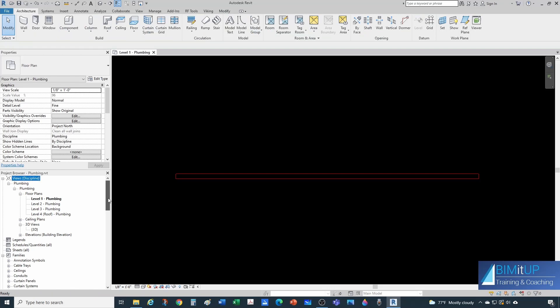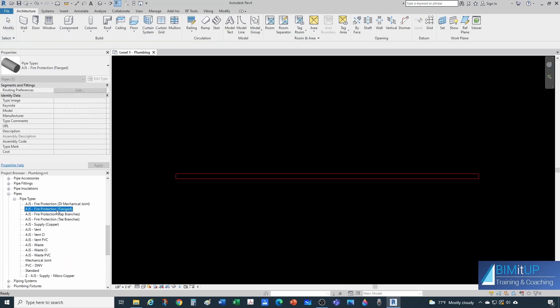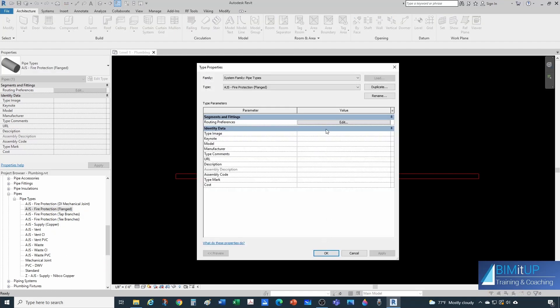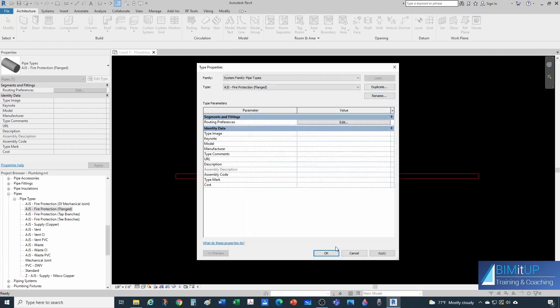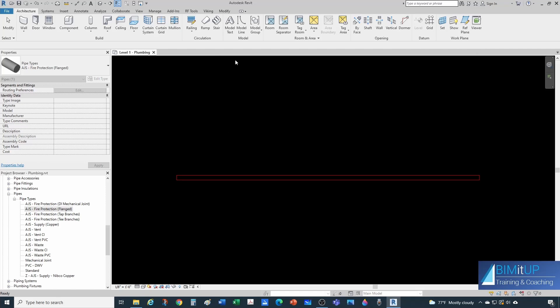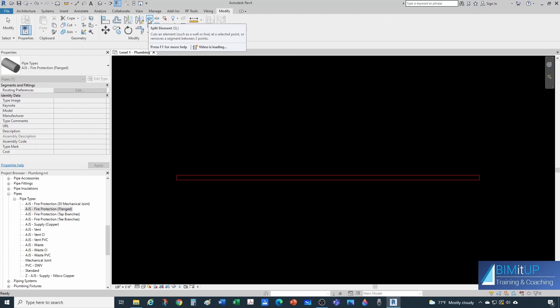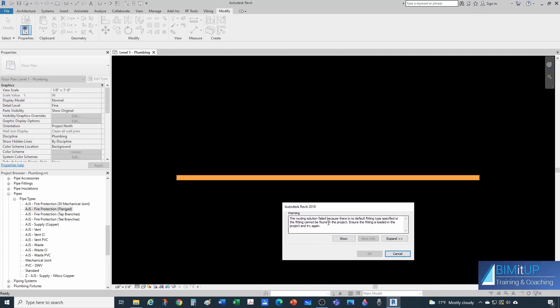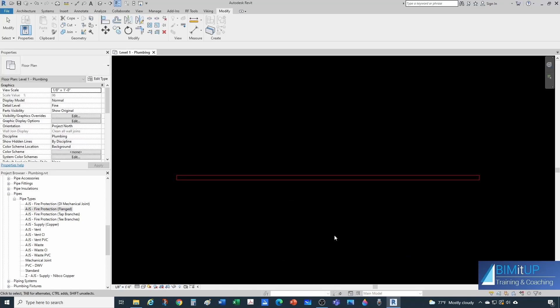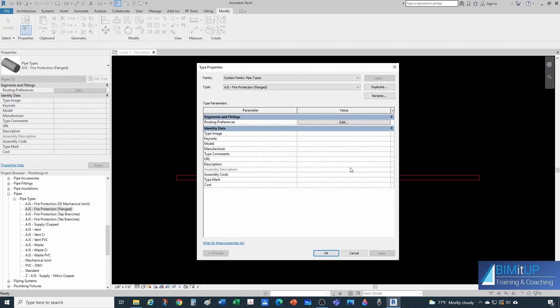Let me show you how splitting works. We're using a fire protection flange pipe type. Under type properties, go to Edit and under Union I'll select none, and under Flange I'll keep none as well. Now if you try to split this pipe using Modify or the shortcut SL, notice you get an error message — it's telling you there is no fitting specified to split that pipe. So let's go back into our routing preferences under pipe types, type properties, routing preferences.